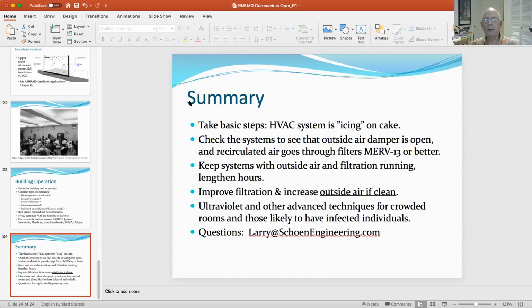But if you're convinced that you want to be cautious and you want to do that too, some of us are saying, okay, in the very dry weather, humidify to 30% relative humidity. This is only going to come up, as the question has said, in the winter. So it's not something you're going to focus on now. Put this on the back burner for now. If you have a humidification system already installed, maybe you're going to consider turning it on. But please do your maintenance to the highest level. There are other diseases that can be spread from the reservoir of water that sits in the humidification system. And there are moisture problems that can be caused in buildings from higher humidity.